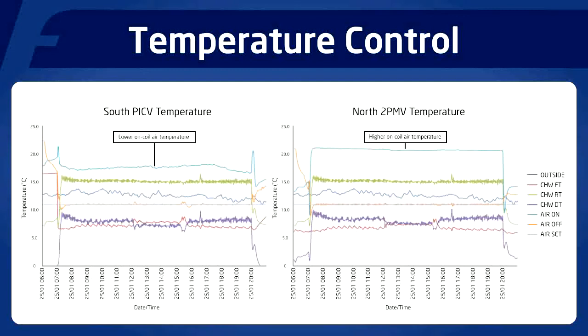This of course means that the valve on the north riser needs to allow more flow, as it's having to work harder to reduce the outlet off-coil air temperature down to the set point. The set point for both north and south is 11 degrees. It should also be noted that the dark blue line represents the outside air temperature, and as the data was collected on the same day, obviously the outside air temperature was identical in both the south and the north riser.